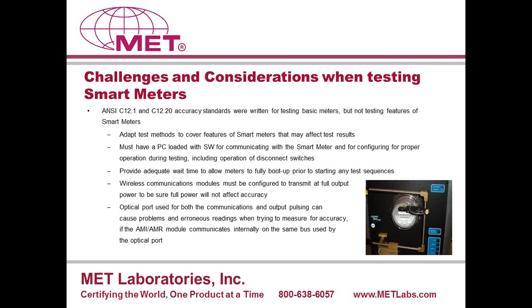So if you have the AMI module installed, or the AMR module installed, we're going to make sure it's transmitting at full power, for example, to be sure that that doesn't affect communications, just as an example. Now, in order to do that, we're going to need support equipment for these test programs. So we're typically going to use a notebook computer with software running to be able to communicate with the meter itself. We may need to configure it properly. We're going to need to actuate any disconnect switches if those switches are in the meter under test. And again, assure that communication is established and that we can see not only the meter being accurate, but you really want to see that when you poll the meter through the wireless module, it's also reporting the same register, and you don't have any issues there.